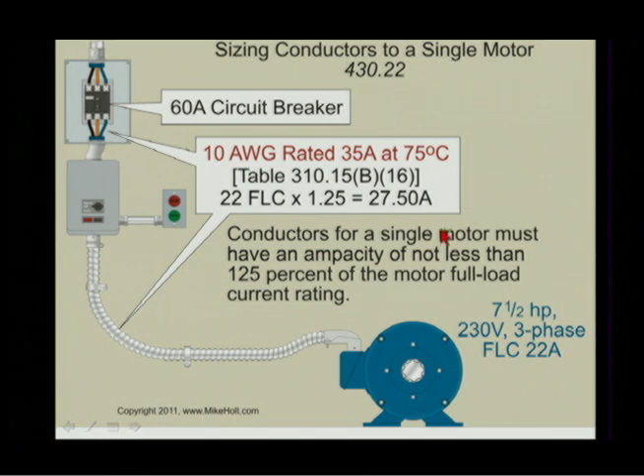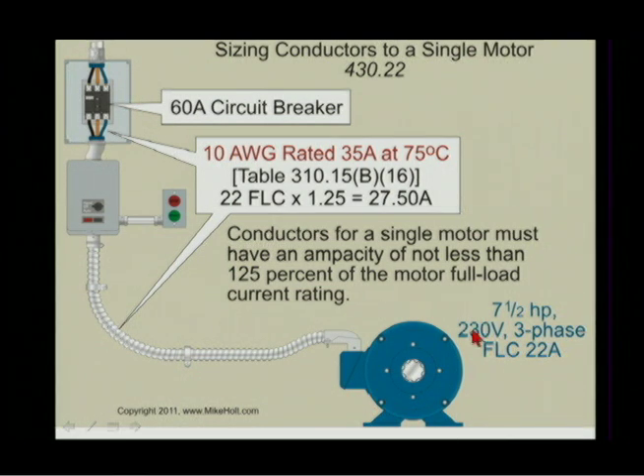Let's work an example. We size the conductor at no less than 125% of the full-load current per 430.22. The example is a 7.5 horsepower motor at 230 volts, three-phase. Go to Table 430.250 in your code book, look up 230 volts three-phase, go down to 7.5 horsepower — the full-load current listed is 22 amperes.